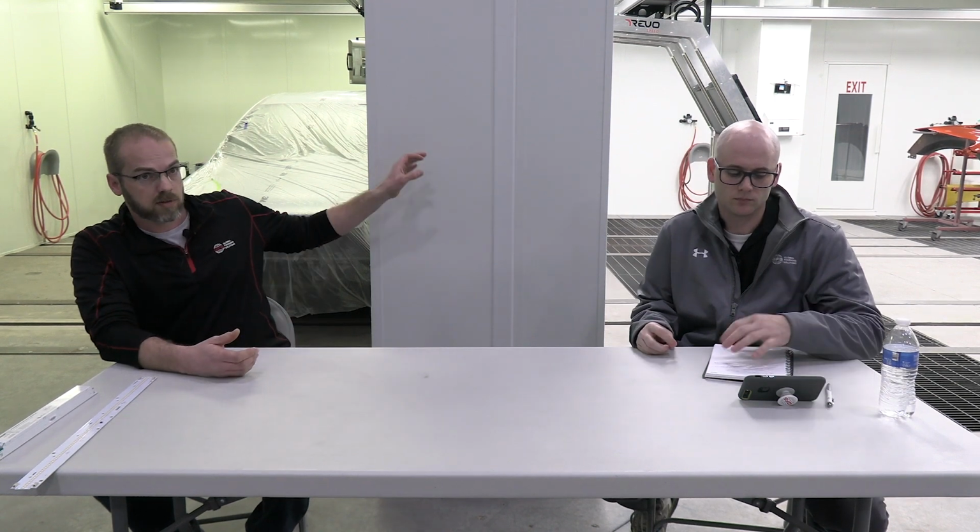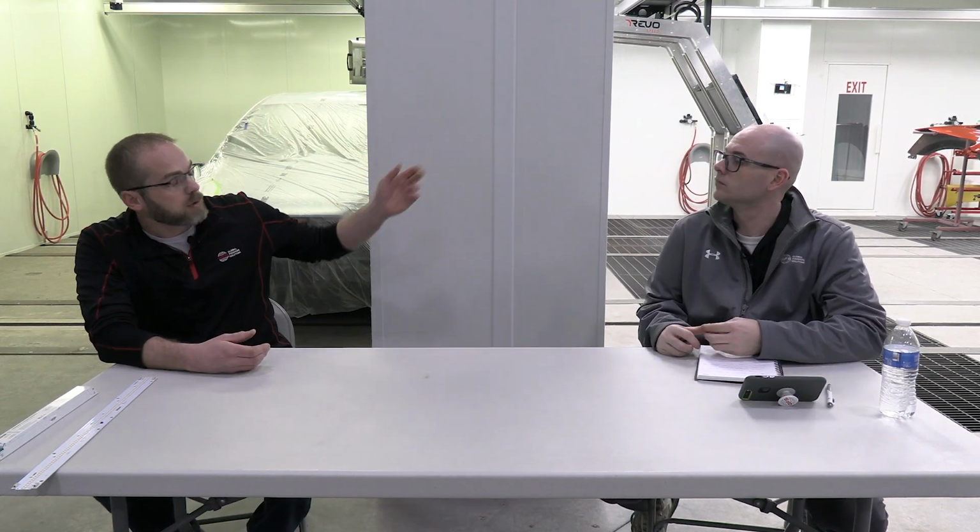These fixtures happen to be a 6-tube fixture on this side. This side is a 4-tube fixture, and for fluorescents, we're drawing approximately 32 watts per tube. So times 4, you're at 128 watts or so on this side. Okay. So you get a significant energy savings, probably around 40% by going with the LED.